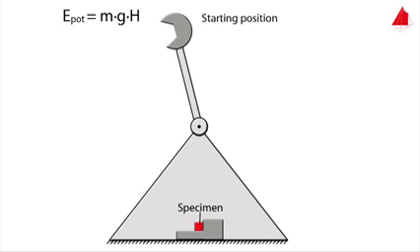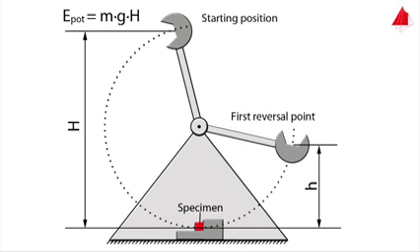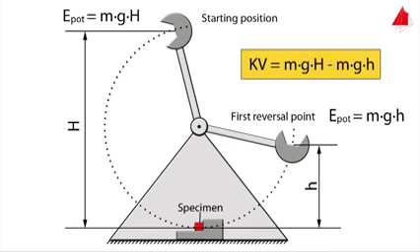Here is the main principle of the measurement. In its starting position, the pendulum only has potential energy. It is given by mass of the hammer, m, times gravitational acceleration, g, times starting height, capital H. After the pendulum has been released, the hammer moves downwards, hits the specimen and then only swings to height, small h. Exactly at the first reversal point, the pendulum again only has potential energy, which is m times g times small h. The energy that has been absorbed by the specimen is called notch impact energy, KV. It corresponds to the difference between the two potential energies.